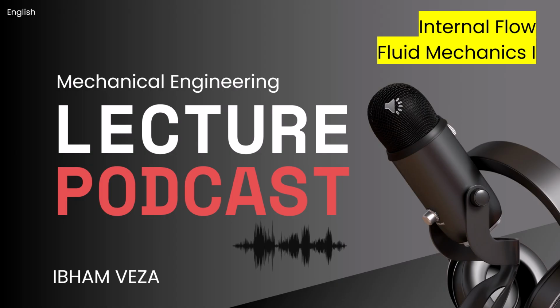Absolutely. This is where things get really exciting. Ultrasonic flow meters are a fantastic example of non-intrusive measurement. They can often just clamp onto the outside of an existing pipe, no need to cut into it, no need to stop the process. They work by sending ultrasonic sound pulses through the fluid. Some measure the difference in travel time for pulses going with the flow versus against the flow. Others use a Doppler effect, measuring the frequency shift of sound waves reflected off particles or bubbles in the fluid. It's similar to how a radar gun catches speeders, or how the pitch of an ambulance siren changes as it passes you.